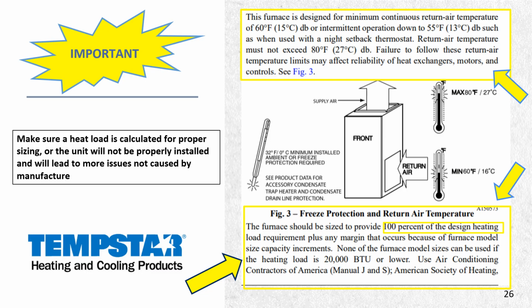One thing too that we see, we hardly ever see this or talk about this, but the furnace is designed for minimum continuous return air temperature of 60 degrees and intermittently at 55. So make sure if you're introducing fresh air into that return, keep in mind that the return air coming from the house is what needs to be returning in that return air, not that fresh air going in, because you could have some issues with moisture going into your heat exchanger. So keep that in mind.